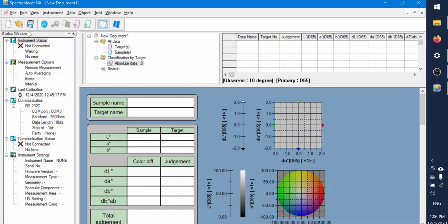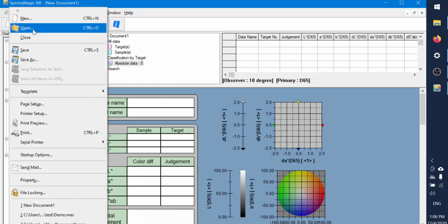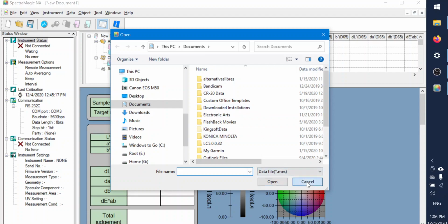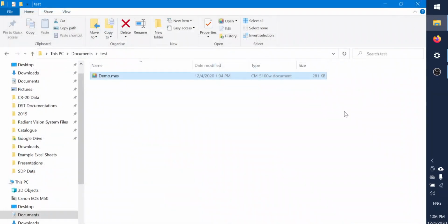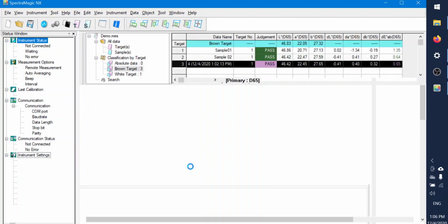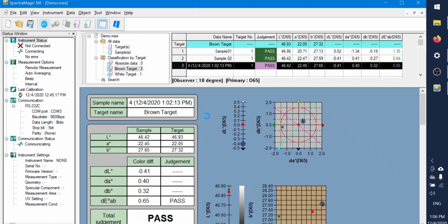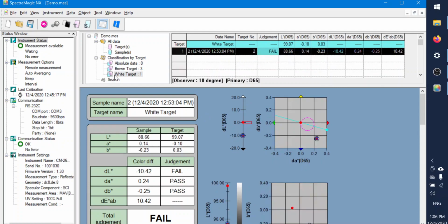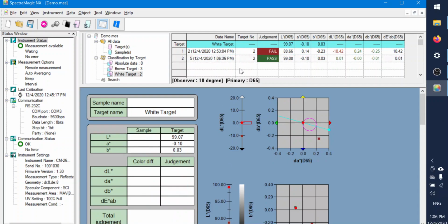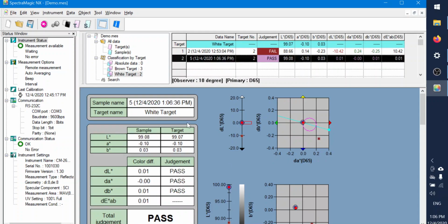So if I would like to resume my measurement, I would have to go back to File, Open, and select my file location. So the most convenient way would be to locate the save file and open up directly on the save file, and this will allow you to continue the measurement. So I will continue on my white target, for example. So I'll place back my equipment on the white, and I will click measure sample. Okay. And it provides me the latest measurement, and I can continue my measurement.